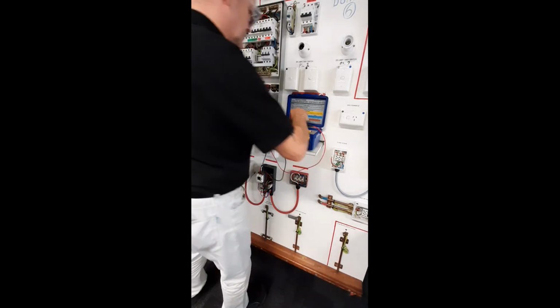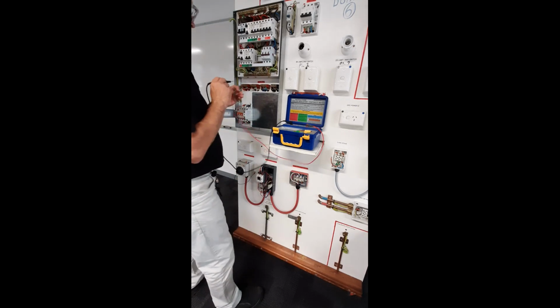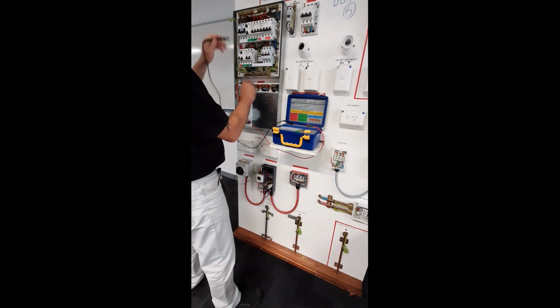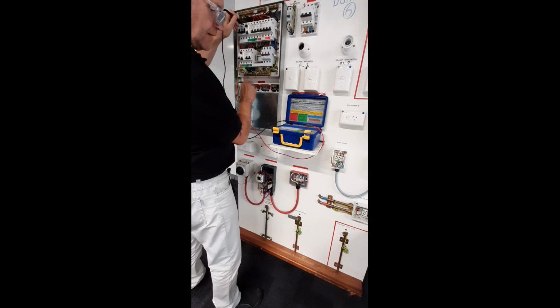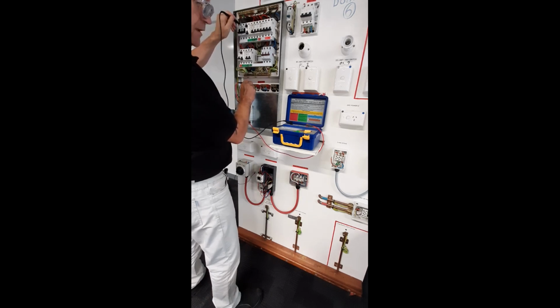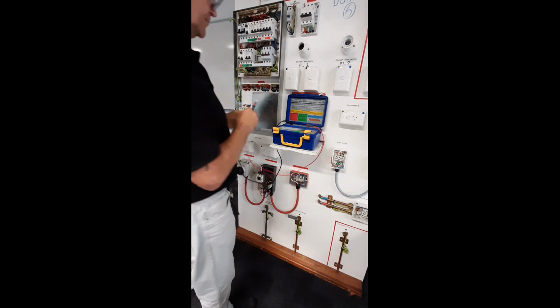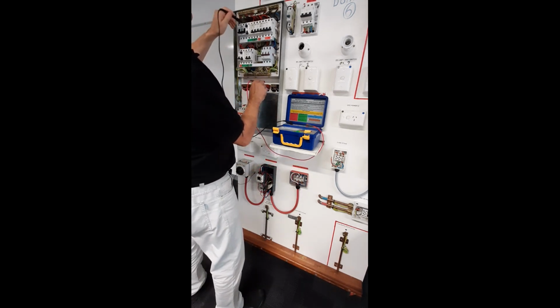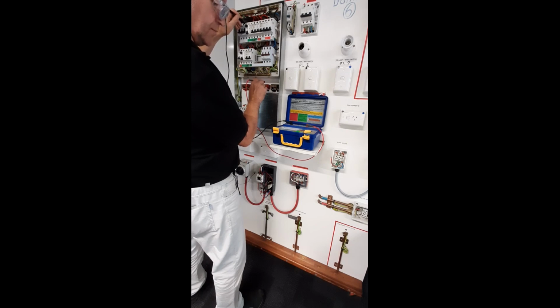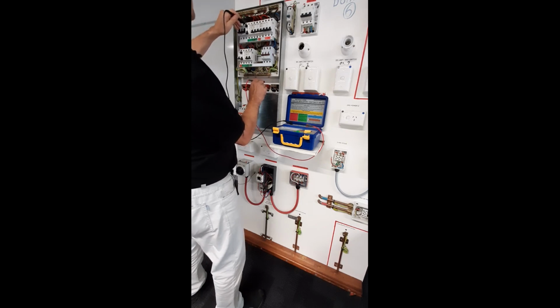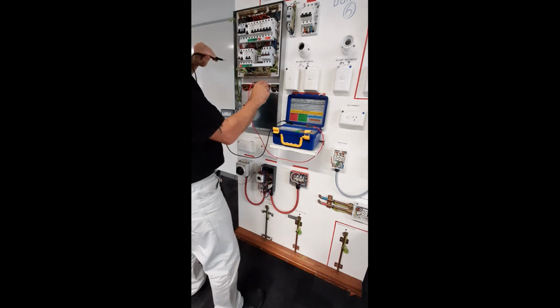Next, the white phase. Again, I have approximately 0.05 of an ohm. I have infinity on the red phase, infinity on the blue phase, and infinity on the neutral. Blue phase. Continuity, approximately 0.05 of an ohm. I have infinity on the red phase, infinity on the white phase, and infinity to neutral.